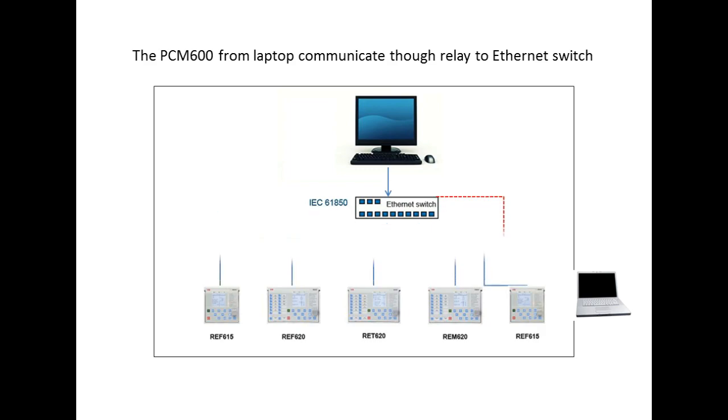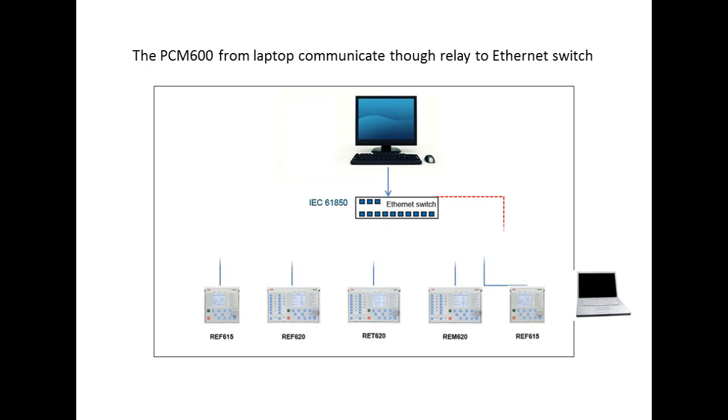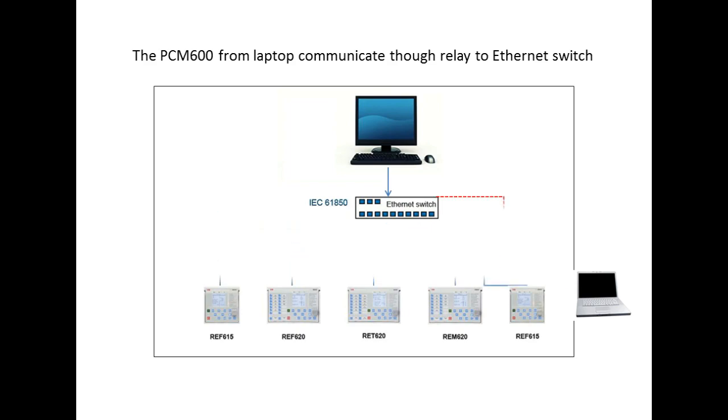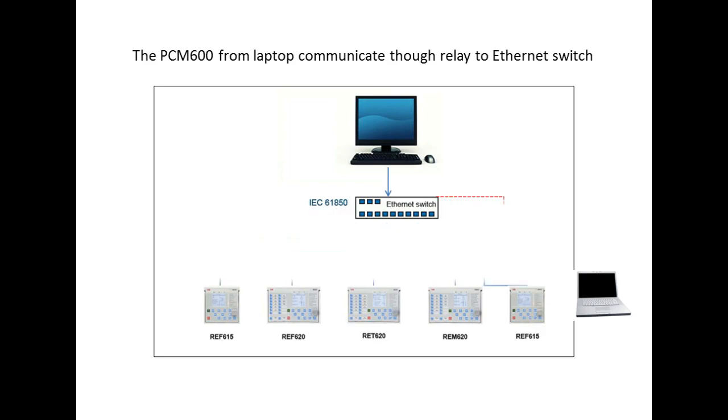The communication is possible because all relay networks will be in the same IP network. All relays send and receive information from ethernet switch, through which our laptop will also get communication. This you can clearly see in this SLD diagram.